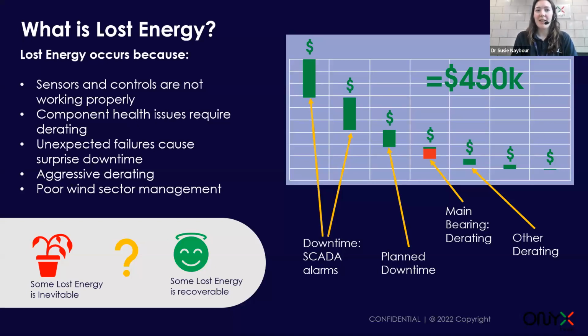You might also have cases where there are health issues on components in your turbine. For example, you may have a main bearing issue, and because of that, you make a decision to derate the turbine, reducing the maximum power it can produce while that component is in a damaged state. That could be losing you quite a lot of production. In some cases, we've even seen the amount of time it's been derated and the cost of that is so expensive compared to the price of the component in the first place. So you have to be careful you don't end up with this kind of indefinite derating.